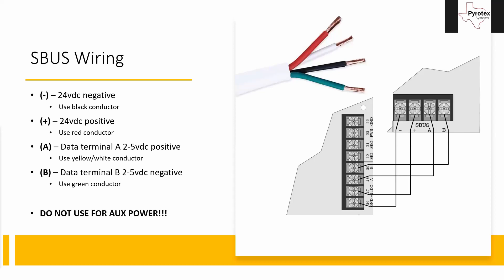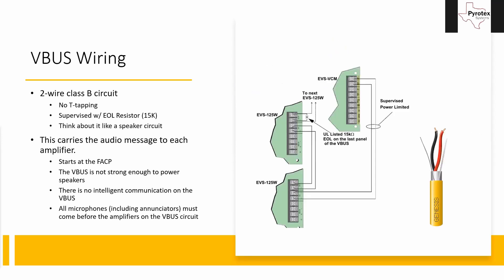To wire SBUS: A always goes to A, B always goes to B, positive to positive, and negative to negative. Moving on to VBUS: as mentioned, this is a two-wire Class B circuit supervised with an end-of-line resistor — specifically a 15K ohm resistor. If you've lost the resistor, that's the value you need. You cannot T-tap it; Class B supervision means supervision is done via the straight-through path. If you have a remote microphone on the job, pull from your panel to your microphone, then from your microphone to the amplifiers. Any other order and it won't work or supervise correctly.